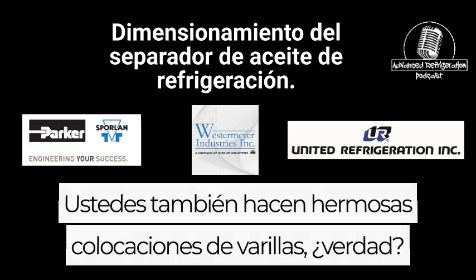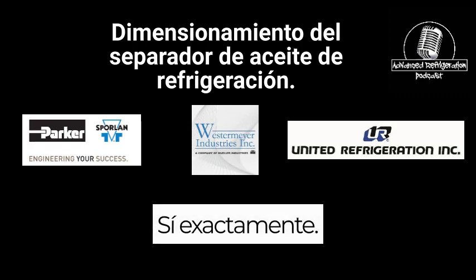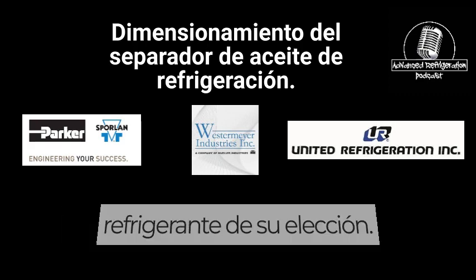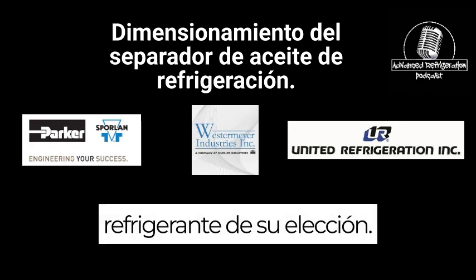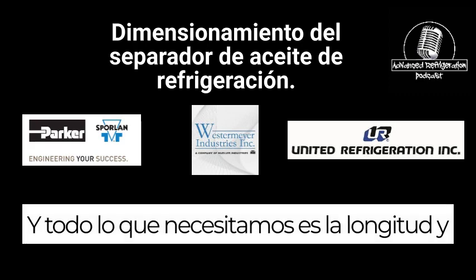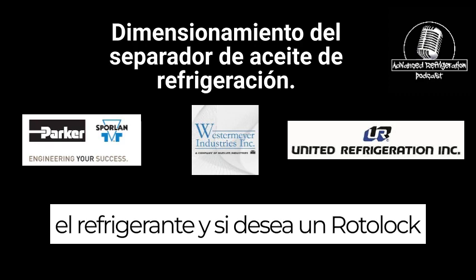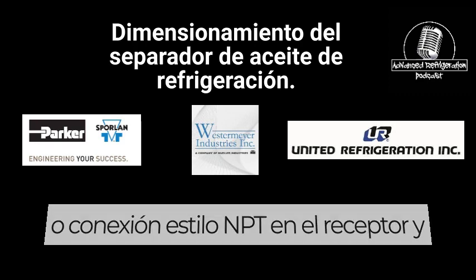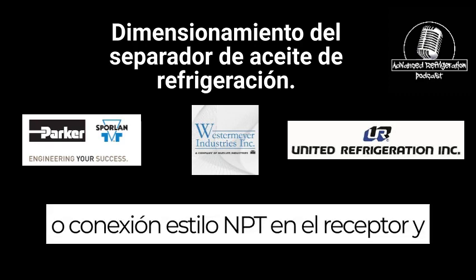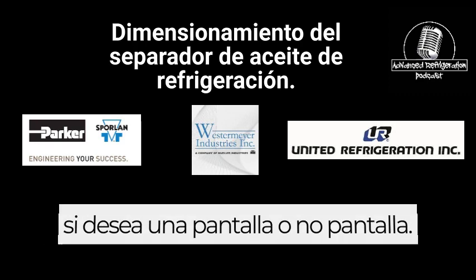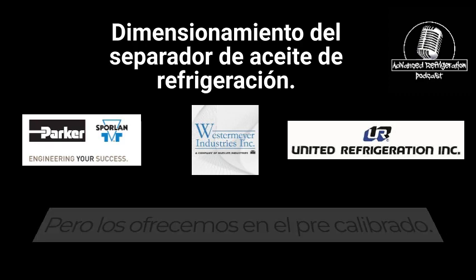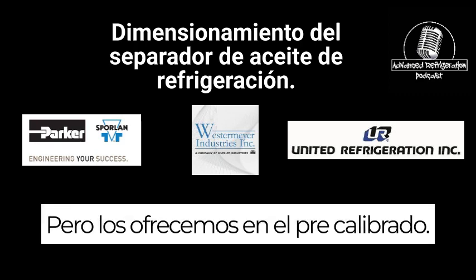You guys make hand rod placements also, right? Yeah, we do. Exactly. And we calibrate them. They're factory calibrated to the refrigerant of your choosing. All we need is the length and the refrigerant, and whether you want a Rotolock or NPT style connection on the receiver, and whether you want a display or no display. But yep, we offer them and they're pre-calibrated.